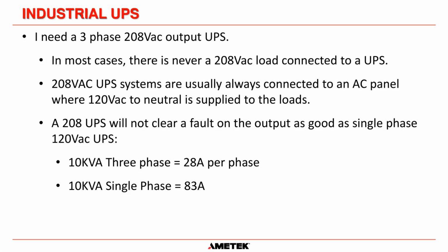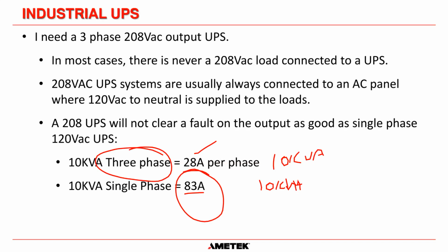You have to remember that a 208 UPS will not clear a fault on the output as well as a single phase UPS, and it's down to simple math. So a 10 kVA three-phase 208 system can only supply 28 amps per phase, because that's the math. It's 28 times 3 times 120, and that gets you 10 kVA. But for a 10 kVA single phase system, it's 120 volts times 83 amps gets you 10 kVA. So you can get 83 amps from a single phase system and 28 amps from a three-phase system.